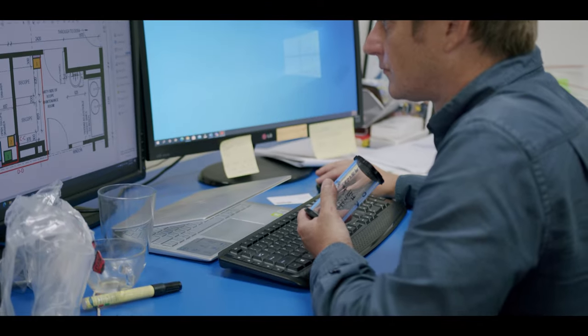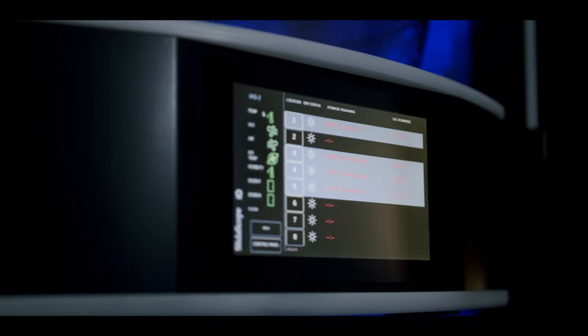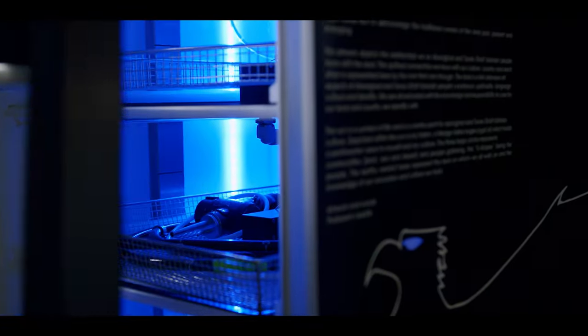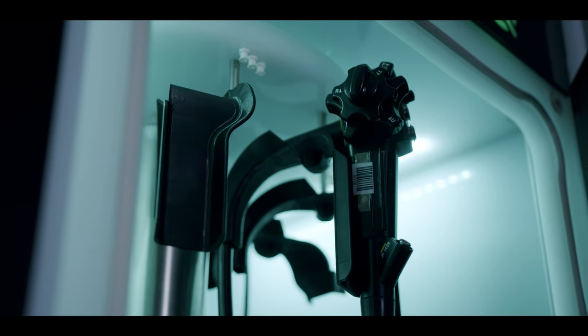With the IQ series we're introducing the latest in smart technology, including channel monitoring — a real-time observation of the drying of all endoscope channels. This technology can check if endoscopes are correctly connected, if they're blocked, and ensure that all channels of the scope are drying at the appropriate rate, ensuring 100% patient safety.